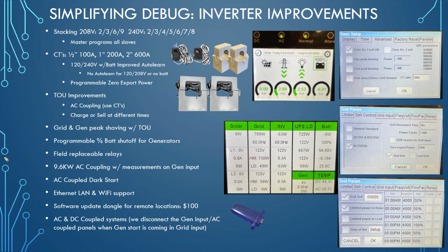But recently, in our latest software update, we introduced a feature where if you do the AC coupling on the generator input, we have a relay on the other side of that breaker, and we can disconnect your AC coupled PV in order to call for the generator, fire up your generator, charge the batteries, turn your generator off, and turn the AC coupled panels back on. That way it's all automated and you don't have to worry about the two power sources conflicting with each other on any given day. It's a really cool feature.